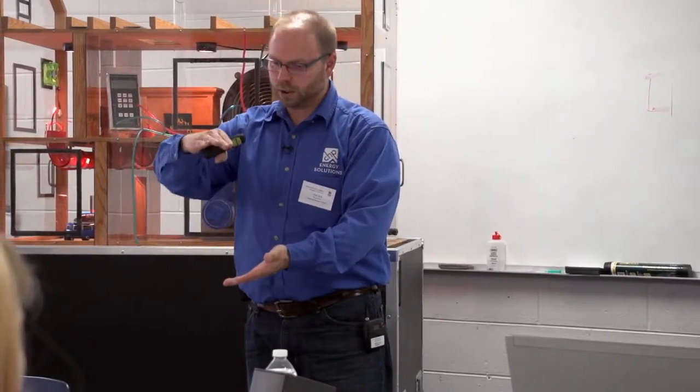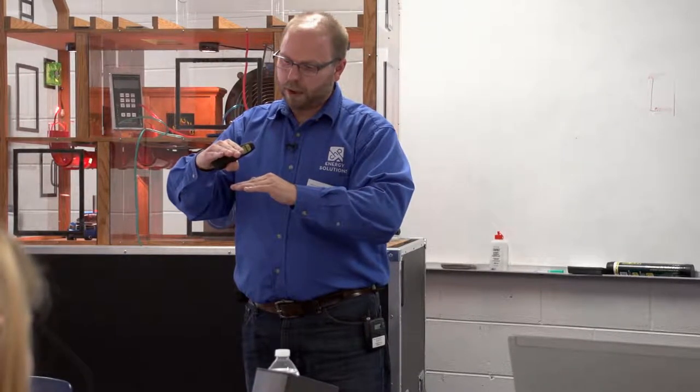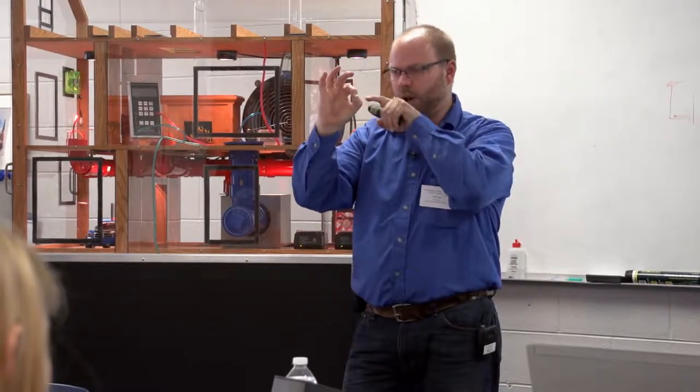We can build boxes over the cans, drywall boxes, allow for 3 to 6 inches of clearance on all sides and on the top, and we can build that drywall box so it's nice and airtight, and we can insulate right up to it. Leave the box extending just a few inches above the insulation so that if it does heat up inside that box, the heat can dissipate to the top of the box, but the box is airtight. Air leakage is a greater loss of heat than radiation or conduction. Once again, a clear passageway, no restriction, will allow for very easy movement of moisture and heat versus if you had to transfer heat through a solid surface, or moisture through a solid surface.